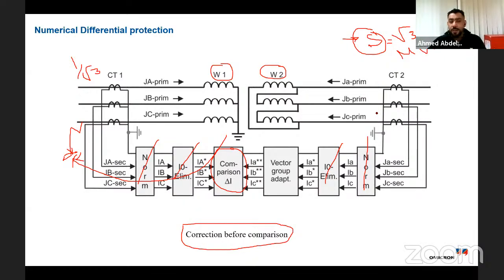I will not do it, because if I have a single phase fault, which is very, very rare on a delta side, the zero sequence current will be trapped inside the delta winding and it will not flow outside. So I don't care about the current going to the CT. This happens, but since I'm standardizing the process for the correction, I need to put I0 sequence elimination for delta, I0 sequence elimination for star. But in case the side is a delta, I need to override this and cancel it, but I will perform it for the other side.